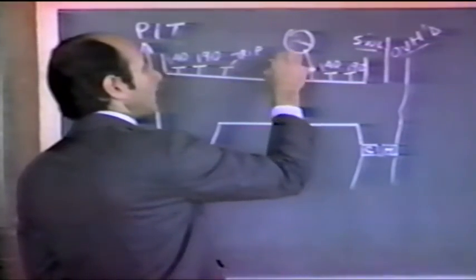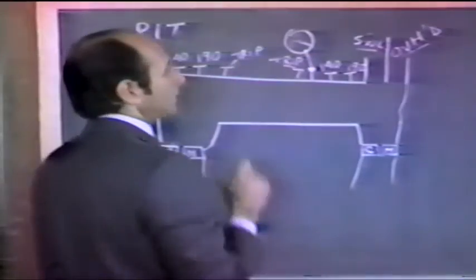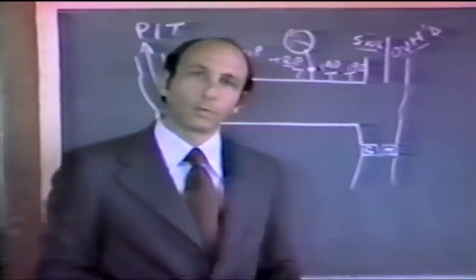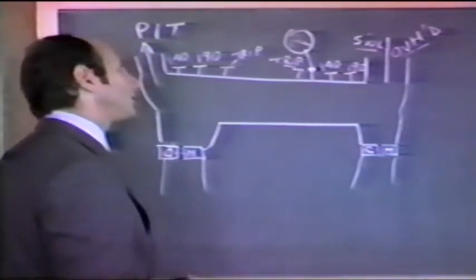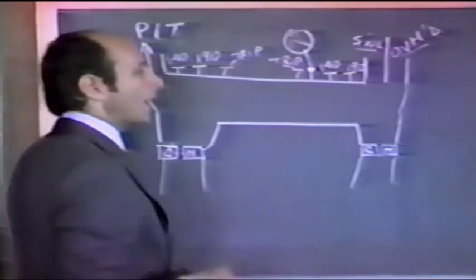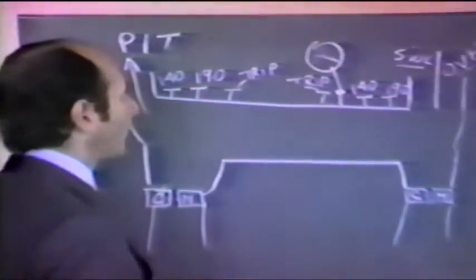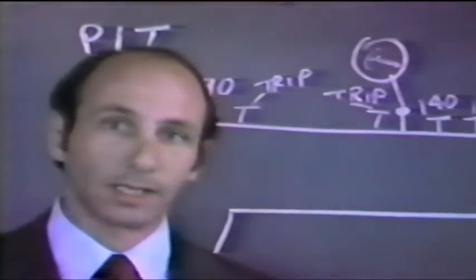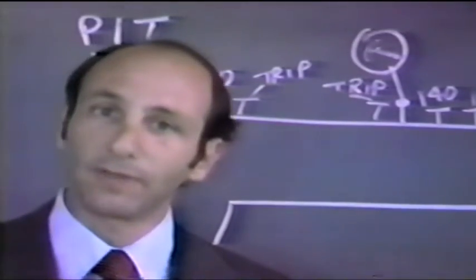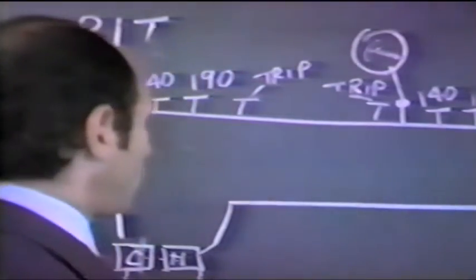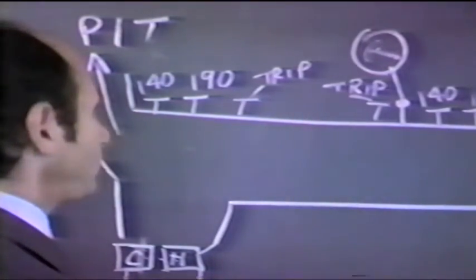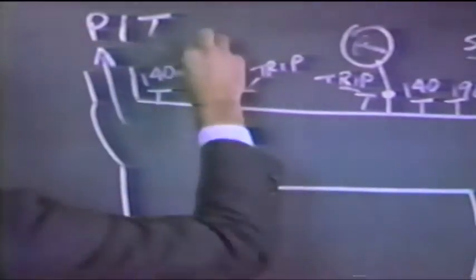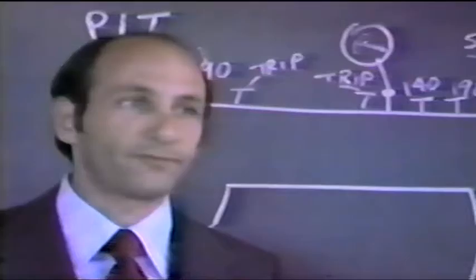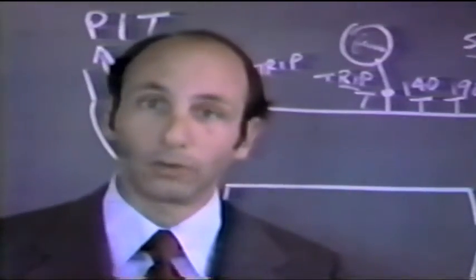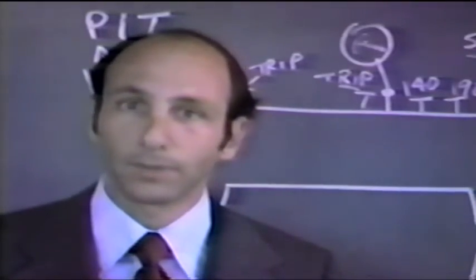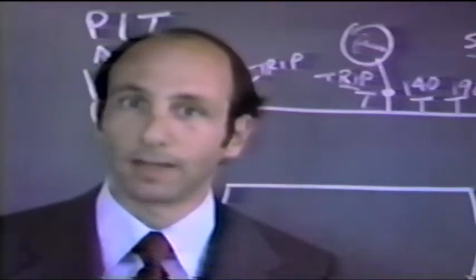And that was the third way that we were talking about of a pack tripping. Okay? Now when would that happen? Well, let's talk about that. At 190 degrees duct temperature, whether we're in automatic or manual, this duct overheat light will illuminate. And one of the things that the duct overheat system does is it will drive the air mix valve to full cold. So why would we ever get 250 degrees? Obviously there's been a malfunction somewhere. Either this switch did not function properly, or maybe the air mix valve physically stuck. Maybe it's a motor-driven valve. Maybe the motor on the air mix valve burned up.